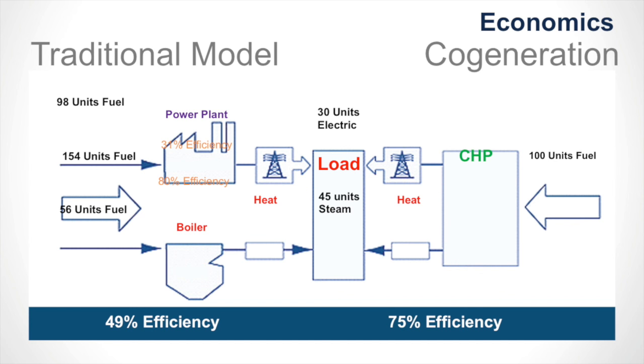So let's say this is Penn College - that's the load. Penn College on a given day needs 30 units of electricity and 45 units of steam, for heating and electricity for lights, fans, and whatever else. So to make 30 units of electricity at 31% efficiency, working backwards, takes 98 units of fuel - that's merely 30 divided by 0.31. For 45 units of steam, boilers operate at about 80% efficiency, so that requires 56 units of fuel. So we've got an efficiency of a load of 75 divided by 154, which is 49%. Do you understand the math?